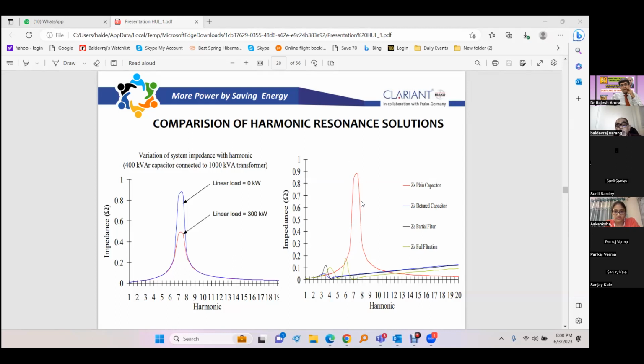So what we do is we use either a 7% reactor, or multiple reactors, maybe for the 5th and 7th frequency, or we can use a very fine-tuned reactor. Instead of say 7%, we can use maybe 5.69% or something. So the level of harmonic mitigation increases with these things. And in all the cases, the resonance point is shifted to a safe place. Either it is between 3rd and 4th, or it is at 4th and 6th, or some place which does not have a harmonic frequency. So the resonance is avoided with the use of reactors along with the capacitors. So this is how it is explained here.